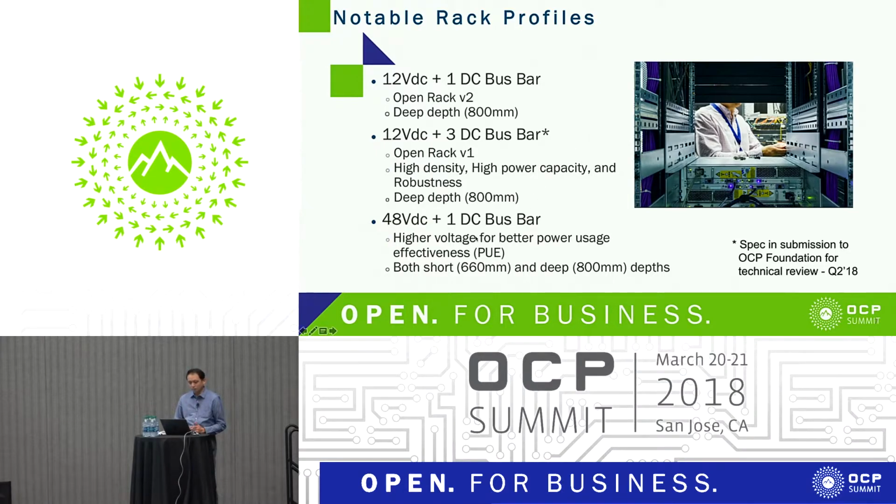The 48-volt DC and 1 DC bus bar is new. The advantage of 48-volt DC is better power usage efficiency from the electronics point of view. And we are going to submit our profile for technical review by Q2 this year.